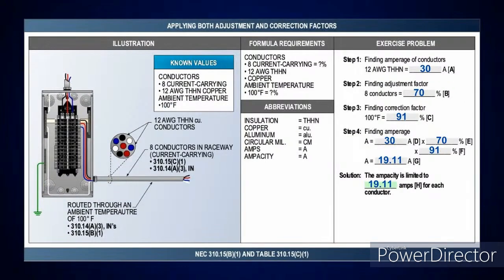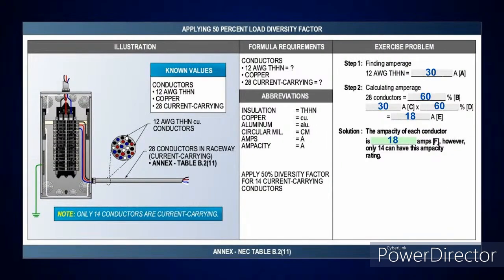Pretty simple. Now you're doing both of them. Exactly the same thing. I've got number 12, it's THHN, so we already did that portion. It's good for 30 amps. You had 8 current carrying conductors. That got me just over the 6, so from 7 to 9, it's going to be a 70% derating factor. For 100 degrees Fahrenheit in table 310.15(B)(1), you've got a 91% derating factor. Just multiply all that together, and it's going to limit each conductor to 19.11 amps. So hopefully everybody's followed that, and everything turned out exactly the way we said it would.